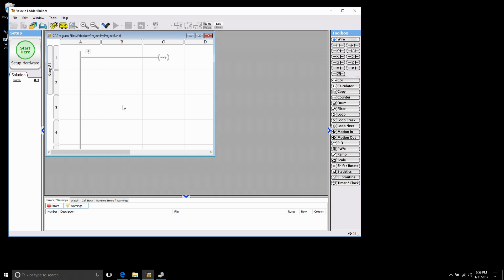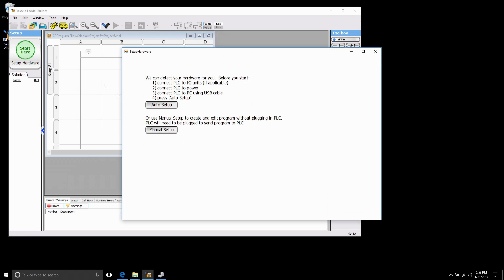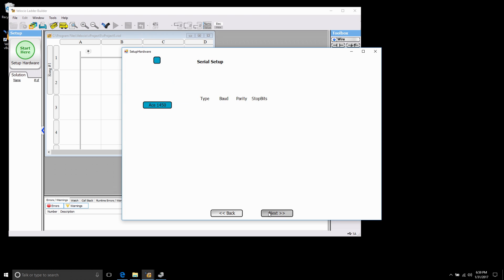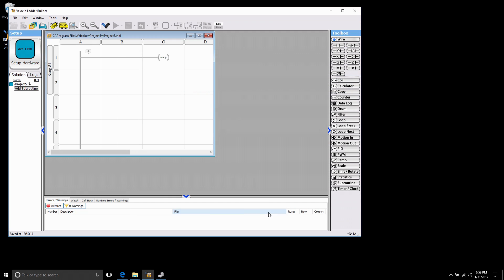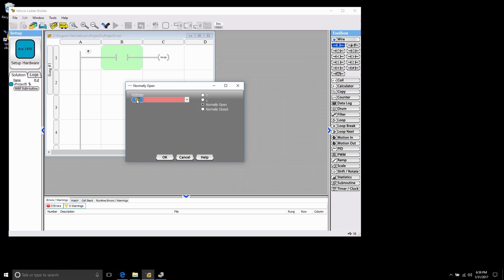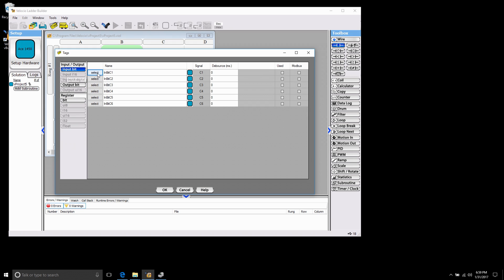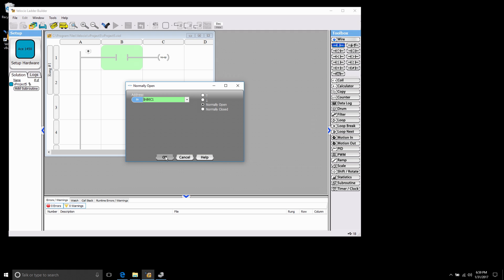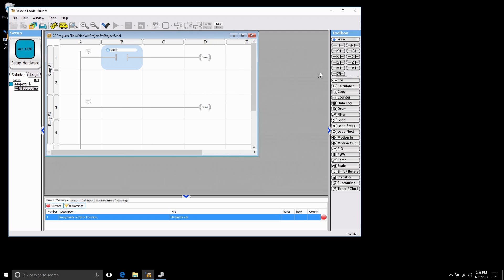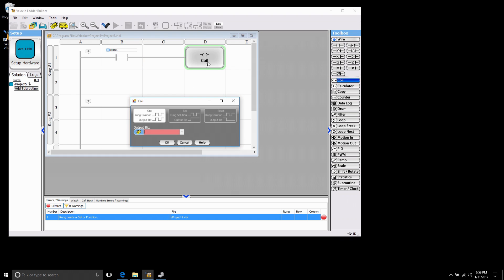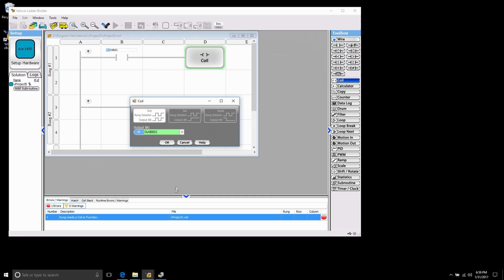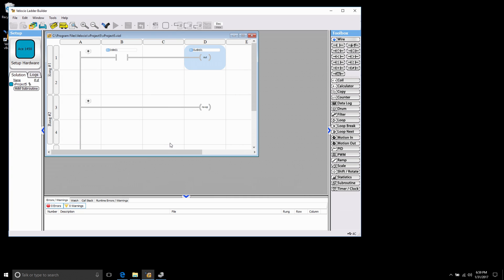Now back in my software the first thing I'm going to do is click this start here button and I'm going to do an auto setup for all the hardware. Quickly go through and basically let it find which hardware I have and create the tags for the inputs and outputs. The first thing I want to do is add a normally open contact to my ladder and link this to one of my physical inputs. Now what I want to do is put a coil and link this to an output. So now I see my input will directly turn on the output.